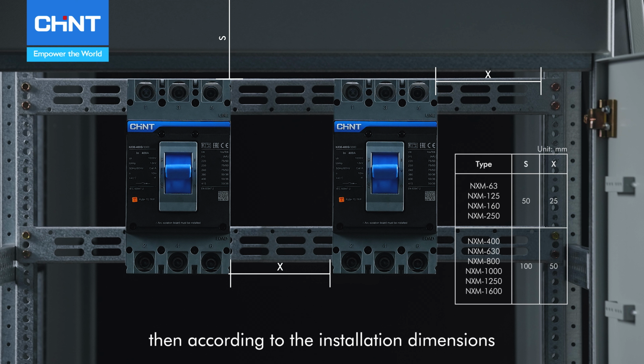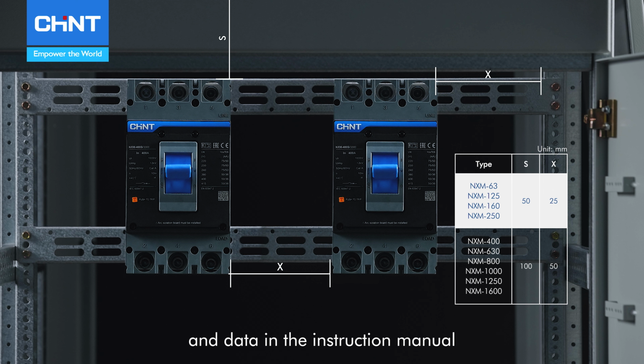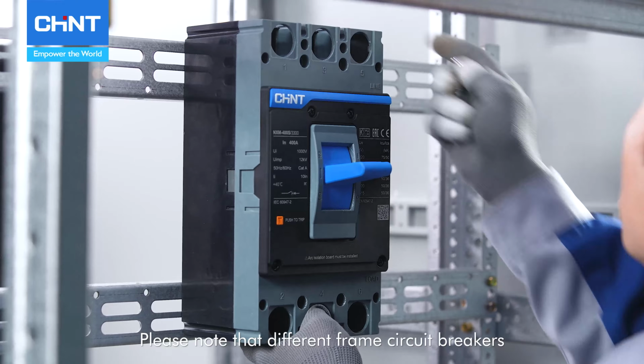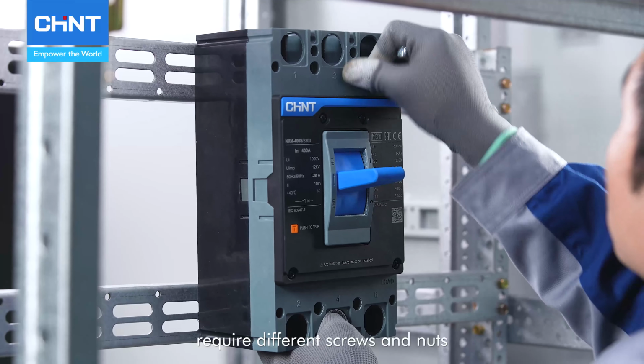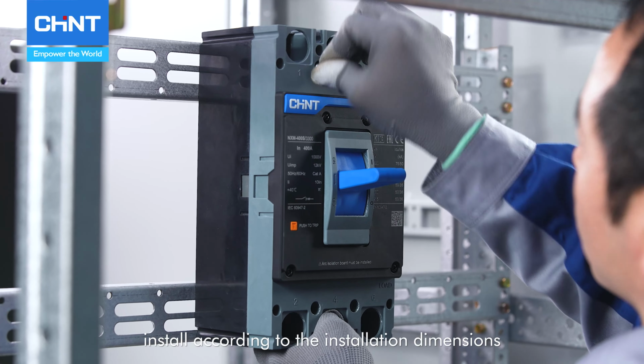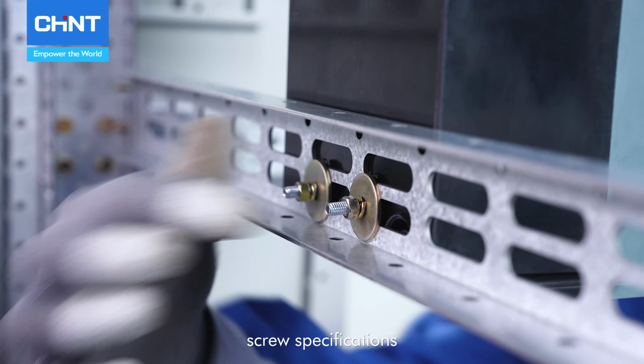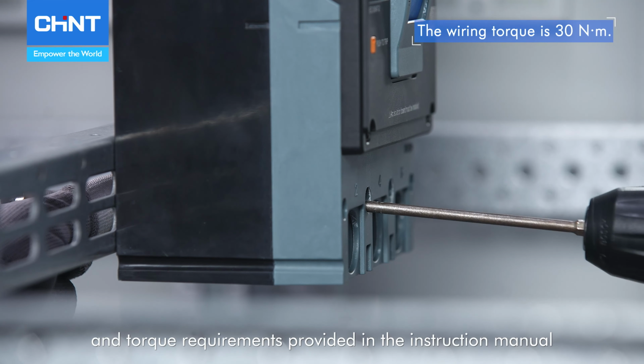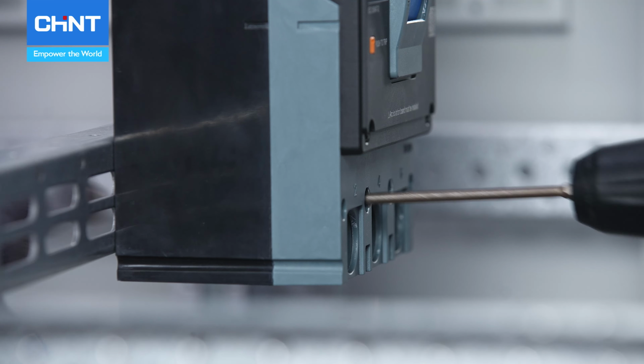Then, according to the installation dimensions and data in the instruction manual, fix the circuit breaker to the distribution board. Please note that different frame circuit breakers require different screws and nuts. Install according to the installation dimensions, screw specifications, and torque requirements provided in the instruction manual.